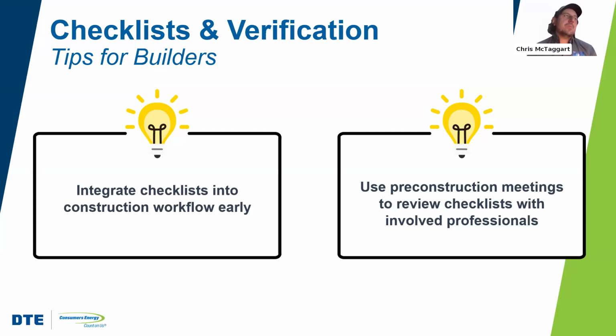So let's imagine a scenario where we're building a home that is on a conditioned basement, and the HVAC equipment is in the basement, and the basement is substantially below grade. It's an 8-foot tall basement, and 6 feet of it is below grade and 2 feet is above grade. That's a pretty standard configuration in Michigan. Well, if your HVAC equipment is in the basement and your walls are only 2 feet above grade, you've got to make sure that your fresh air ventilation then is coming out that rim joist, most likely, in order to ensure that that fresh air intake is at least 2 feet above grade.